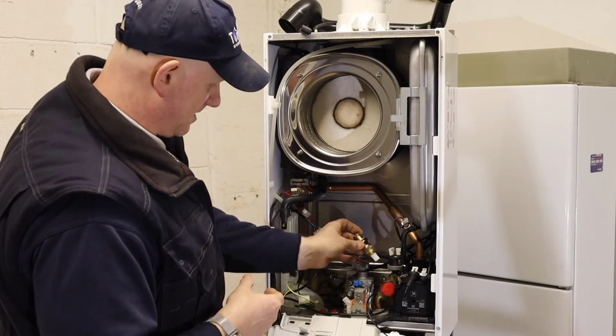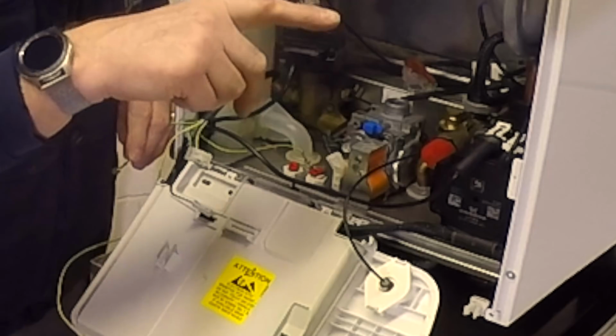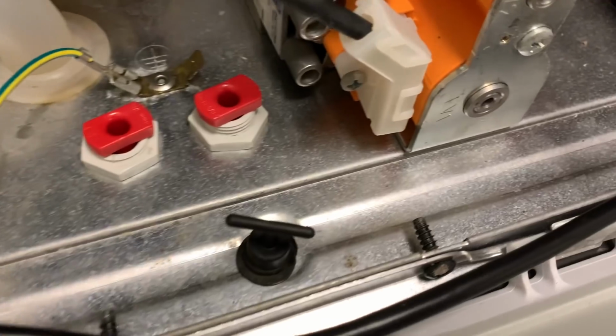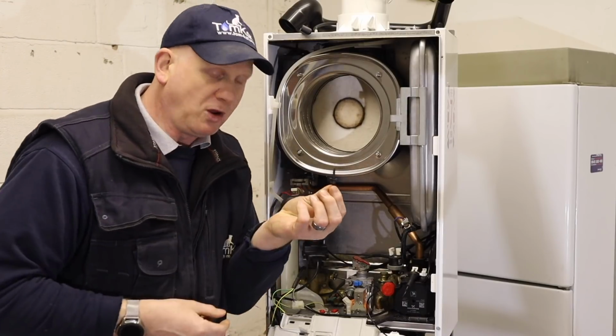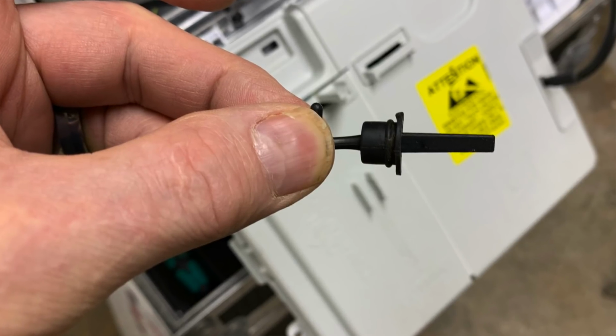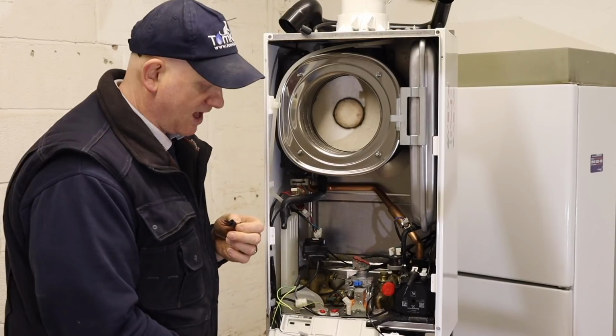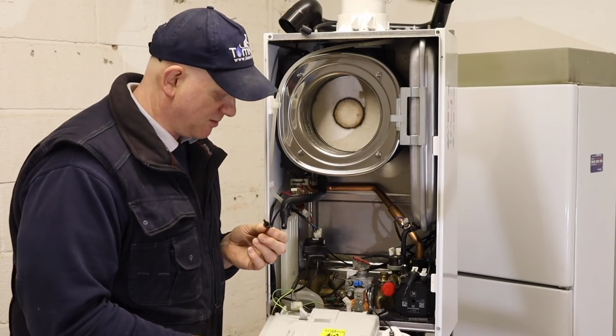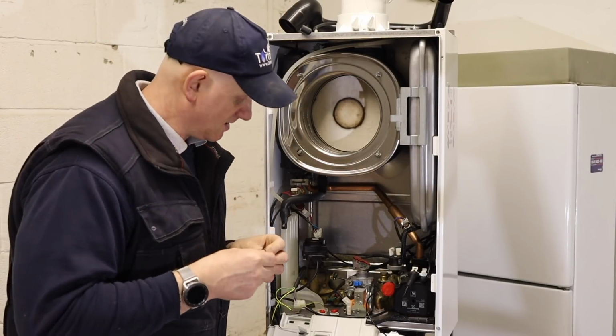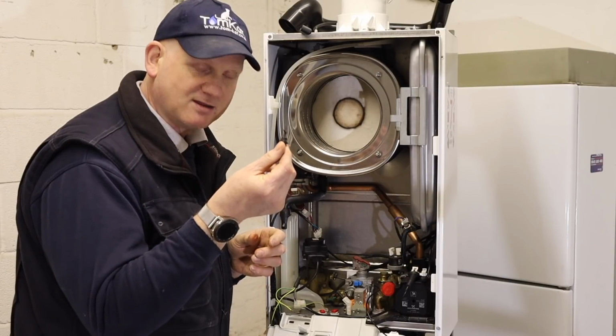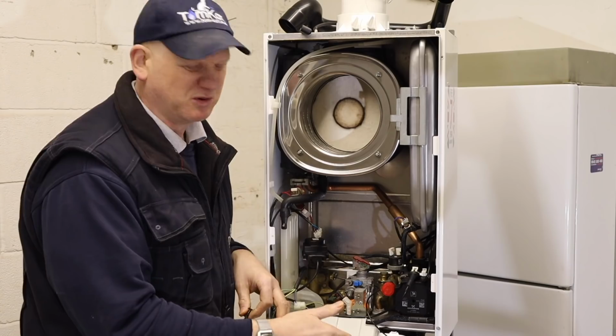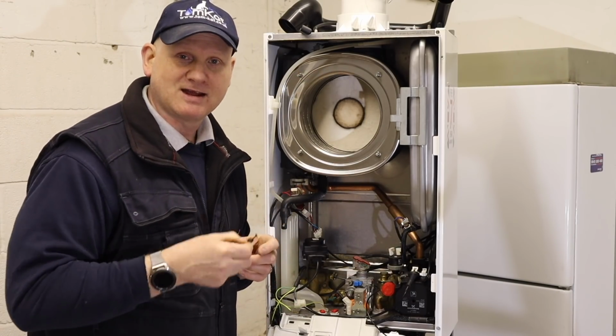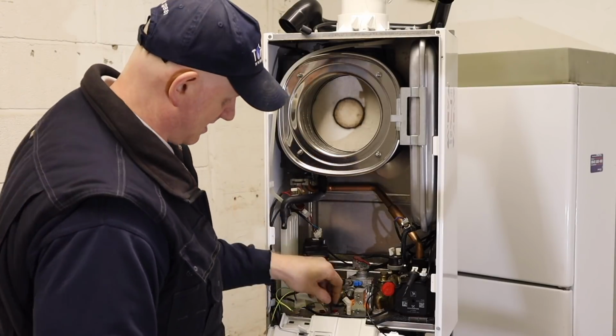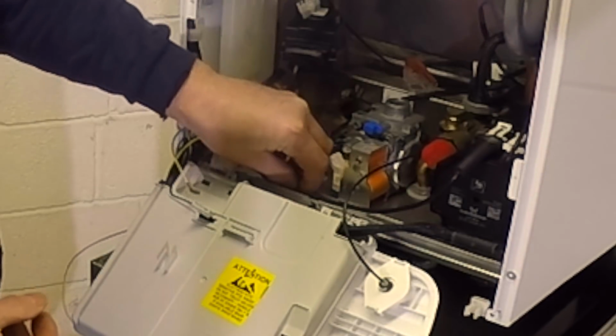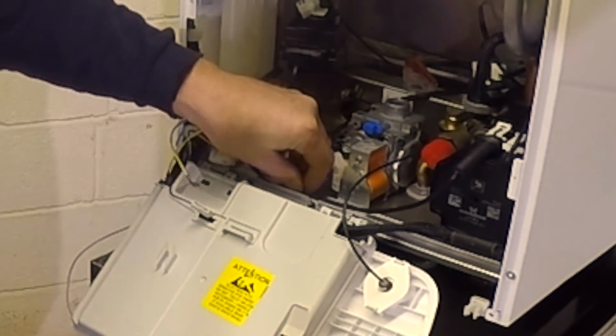Now, what I wanted to show you was in this boiler they've put a drain at the bottom. It's like a groove that goes all the way around the base of the boiler, and they give you this little rubber plug. So you can take the rubber plug out and put a bucket underneath the boiler, and the water will go down there and not all over the board, because you want to protect the PCB. That's a good little touch from Baxi, so you don't get water on the board. You still have to cover the board because you're taking stuff out, but I like that idea. A few other manufacturers give you kind of the same thing, but nice little touch from Baxi - makes it a lot easier to get the water out of the bottom of the boiler.